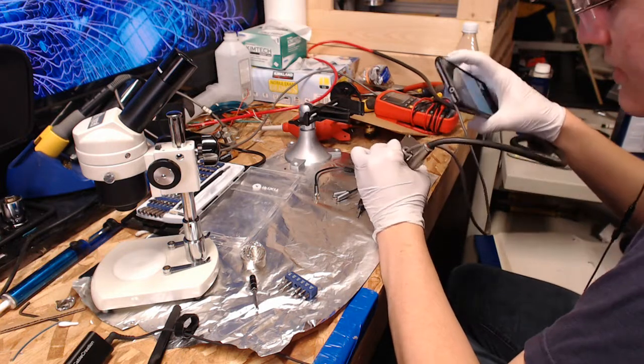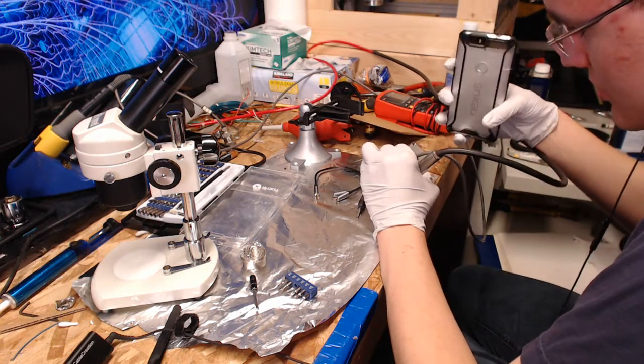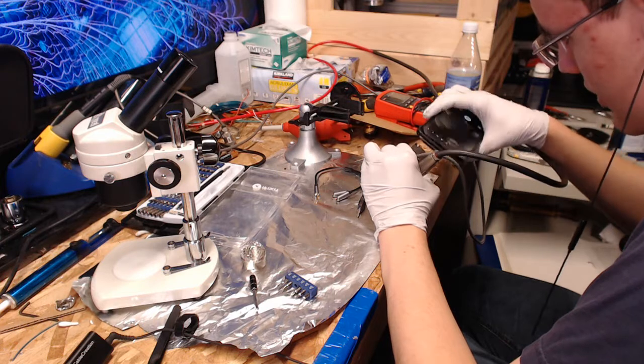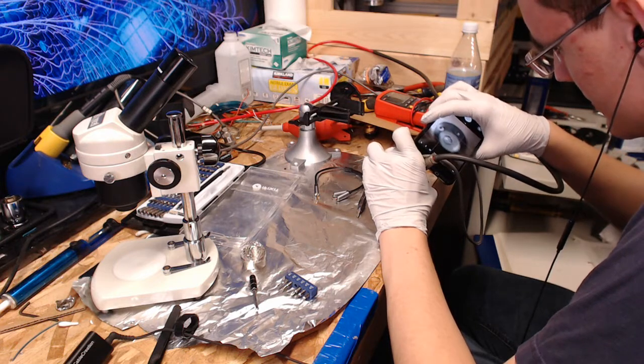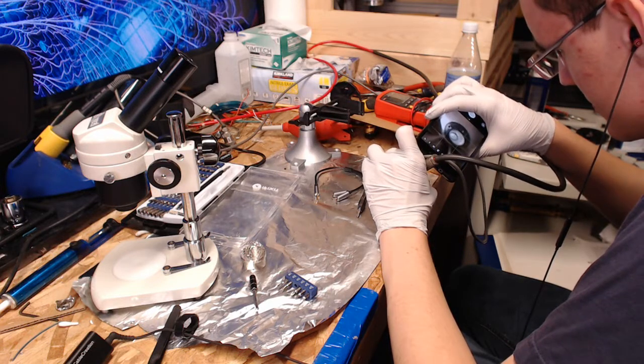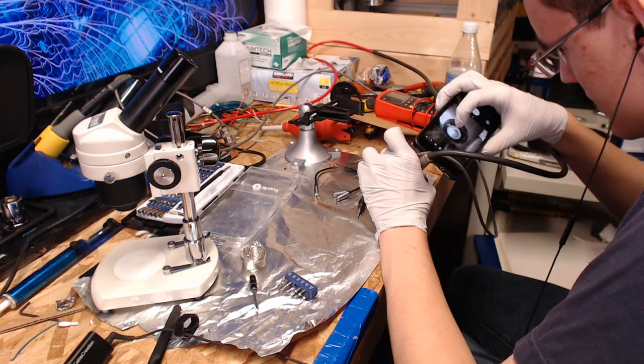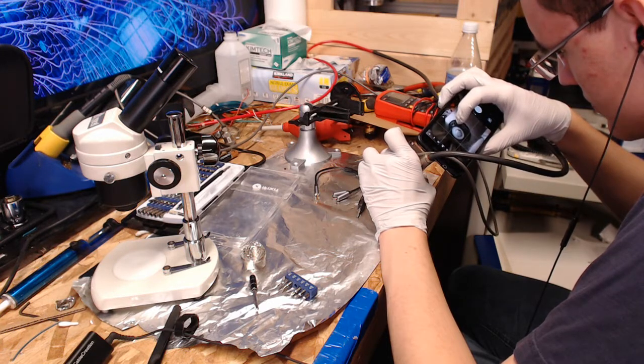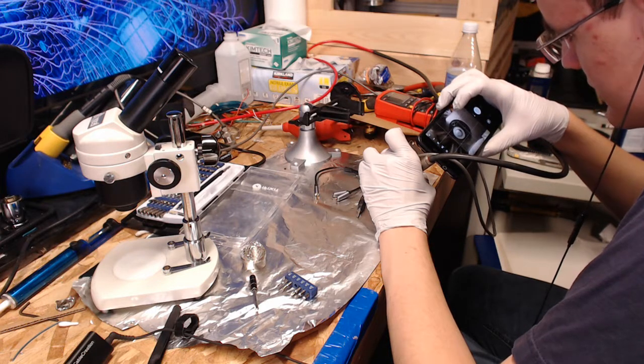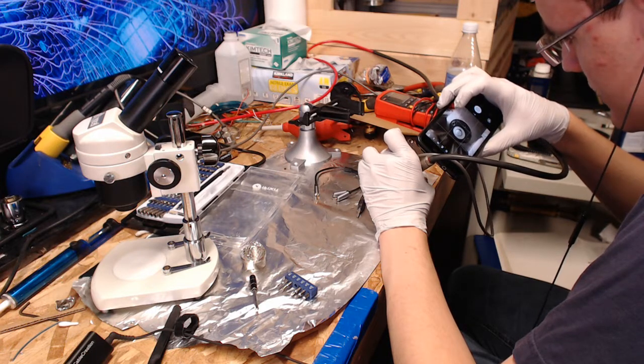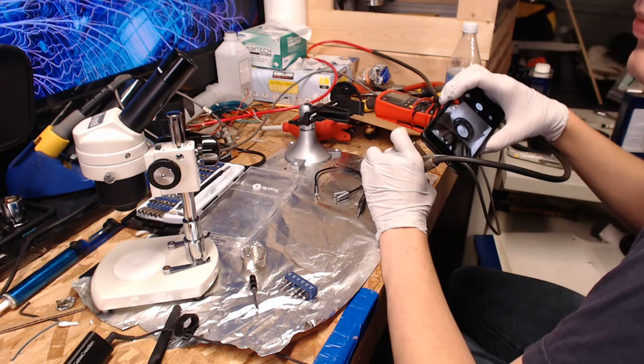Okay, I'm looking at the scintillator from the back side. I can definitely see some damage on it that you can't see from the front side. Looks like it had an arcing incident or something. Sounds like that won't be your primary then. That other scintillator works well enough. It doesn't have any really big noise issues. It's just, in general, it's just degraded, so I just don't get the performance out of the microscope I want.